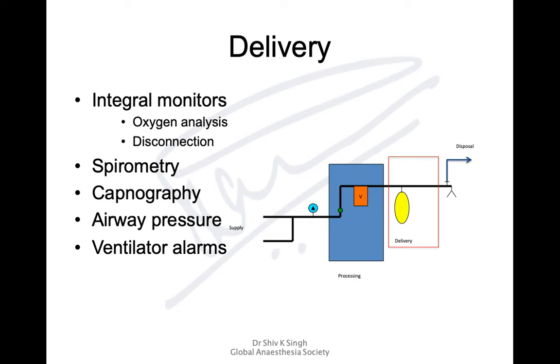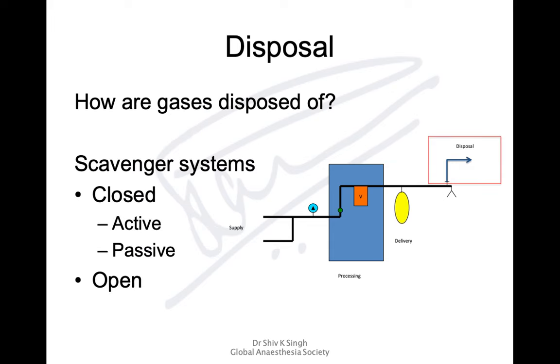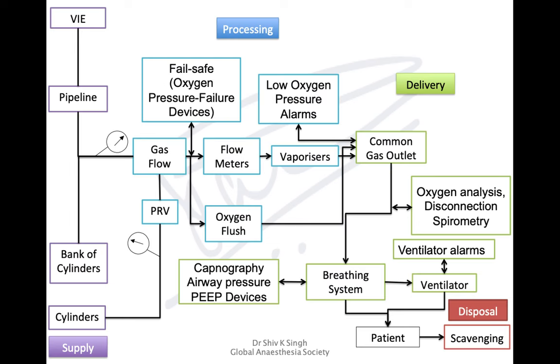There are integral monitors for the oxygen amount delivered to the patient, disconnection alarms within the breathing circuits, integrated spirometry, capnography, airway pressure monitoring devices, and ventilator alarms. For disposal, gases not used by the patient are disposed of via the scavenging system, which can be open type or closed — either active or passive.